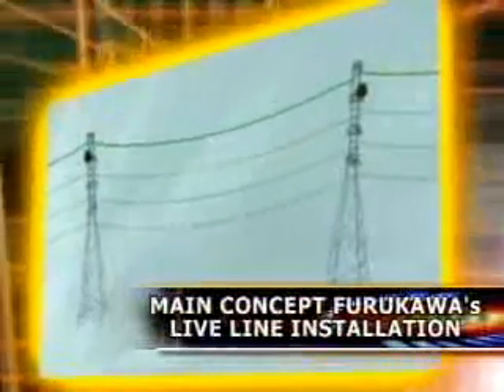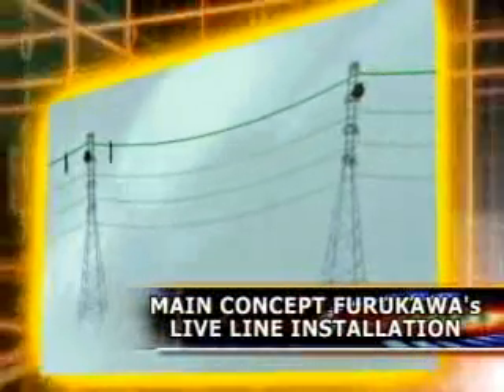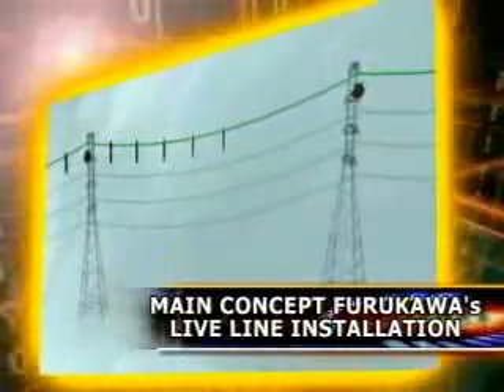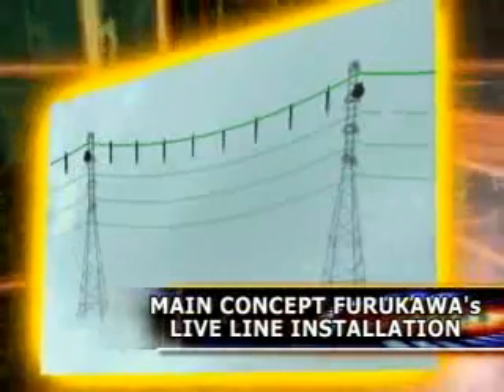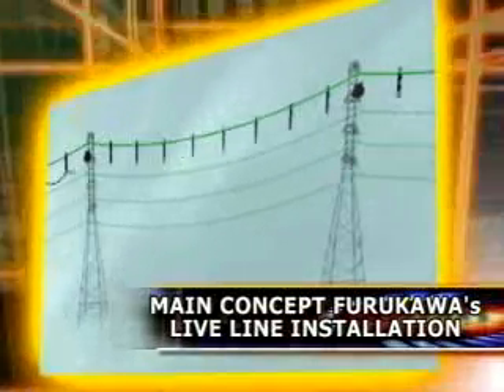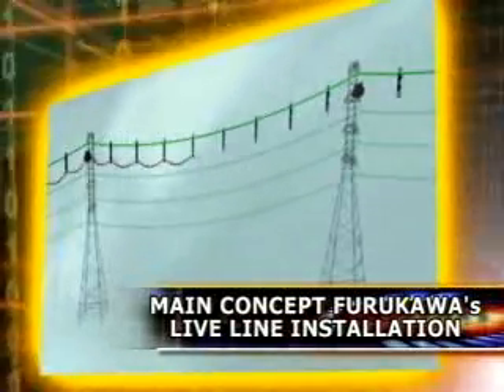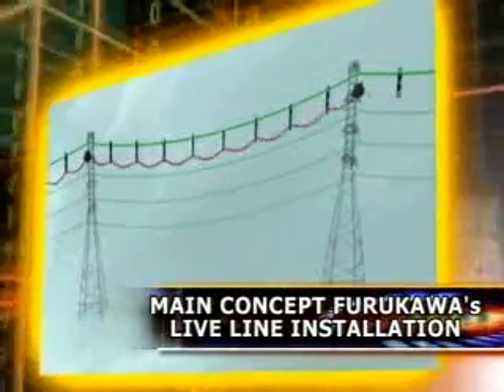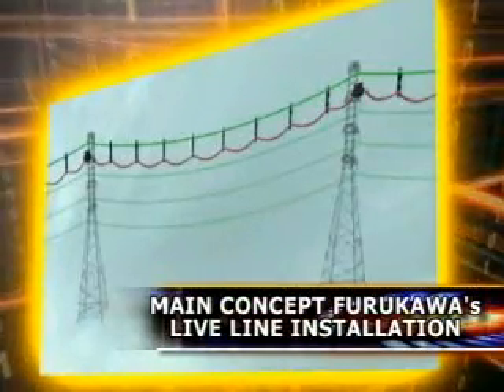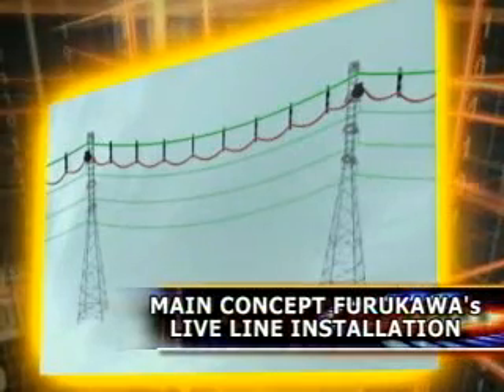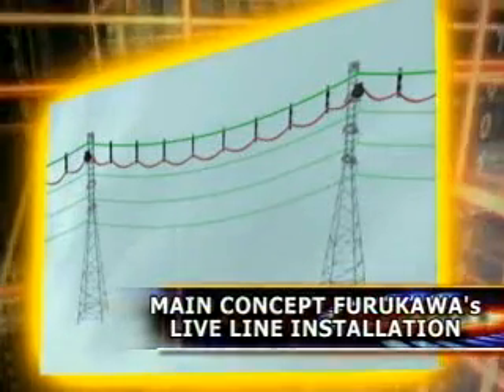The main concept of Furukawa's live line installation is to apply the low-tension stringing method, which can be achieved by reducing the span length between the roller support. Hanging pulley blocks are hung on the existing ground wire at an adequate interval. As a result, the sag is easily controlled to obtain a sufficient clearance from the conductor. The controlling tension will be very low, ranging from 70 to 100 kilograms. Therefore, the use of heavy equipment such as big tensioner and big puller are not required.